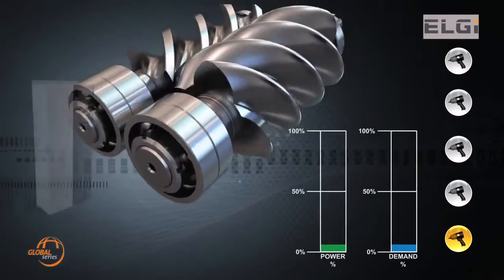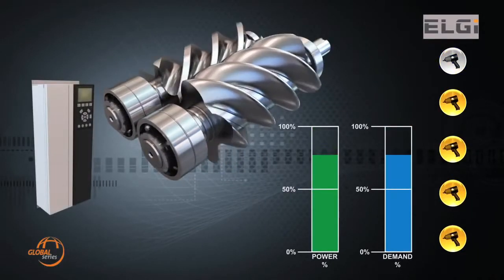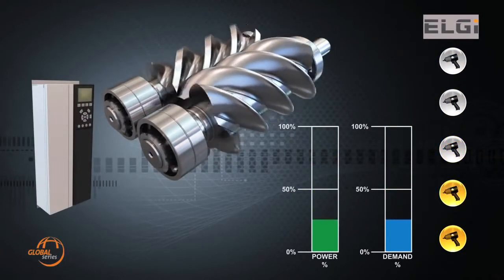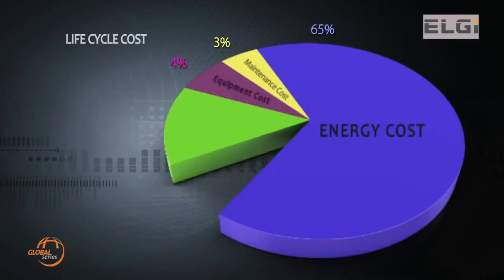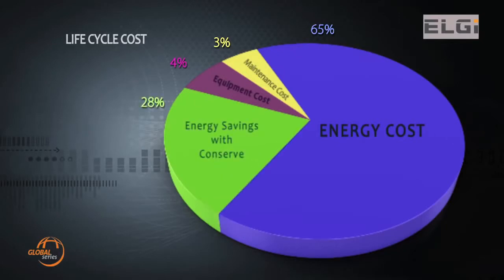Since compressors are not always operated under full load conditions, ELGi Conserve ensures substantial energy savings. Based on load demand, the VFD control varies the frequency of the drive, thereby increasing and decreasing the drive motor speed, which results in 28% substantial energy savings in life cycle cost.